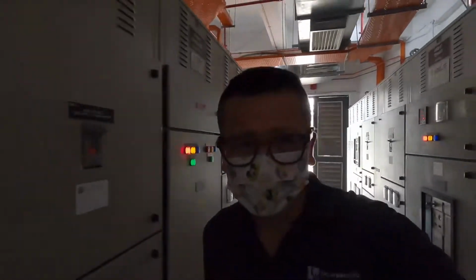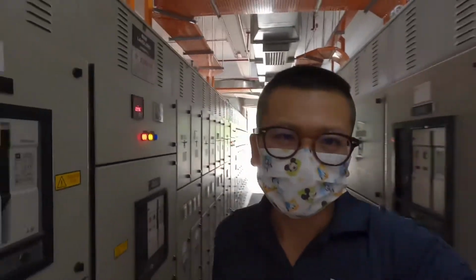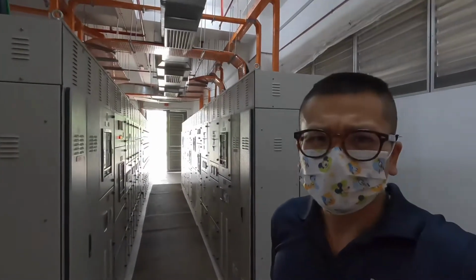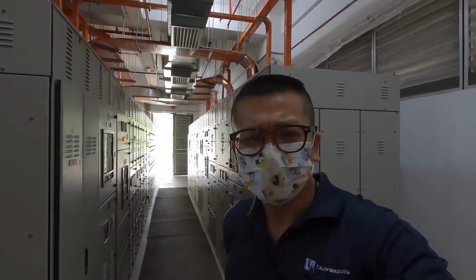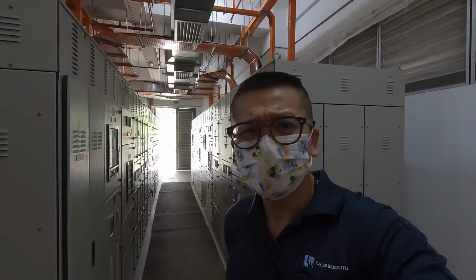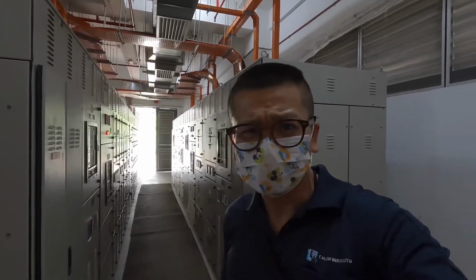Okay, today I'm at Amanja. This is Amanja residences. I'm going to test run the genset under offload condition by using a remote signal from the ATS panel. Currently I'm inside Amanja LV room. First of all, before we test run, we're going to check the parameters.